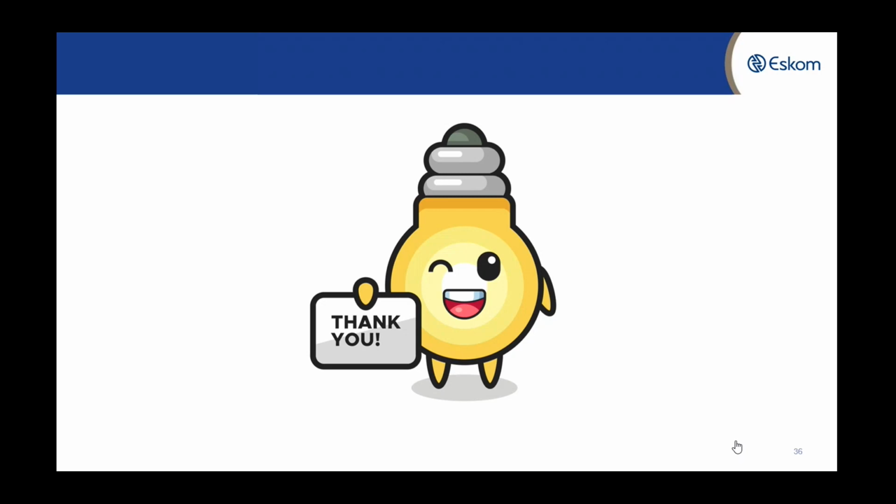He did mention that we're asking for an Eskom installation, that we're looking at EMC testing. We've actually purchased instruments now, and in the near future, I'm saying at about next month or so, we have been trained, so we're going to try and play with the instruments and get that testing done as well for illumination in our stations, because we picked up that with the LED products on the market, some of them do have a lot of noise, and it's going to start interfering with radio signals, and it might be able to interfere with C&I signals and controls as well.